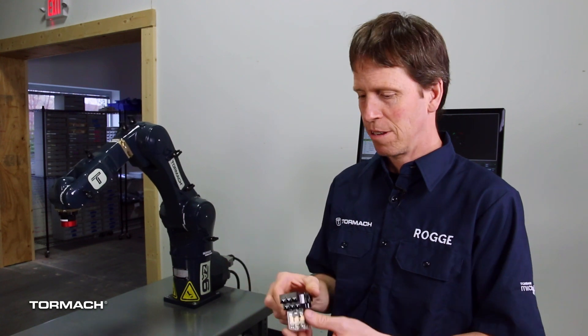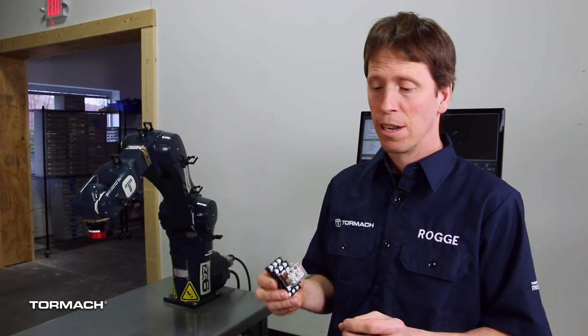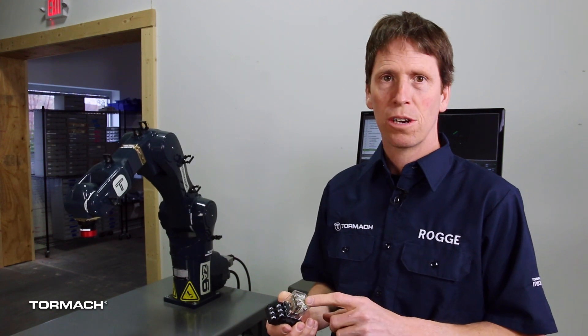Firstly I've got a 24-volt contactor, it's a din rail mount, it's just a simple contactor, but what's important it's a 24-volt DC contactor. Any relay or contactor you're going to want to use for this will be something that has a 24-volt coil. You can't use a 5-volt coil or 12-volt coil or an alternating current coil, it's got to be a relay or a contactor that takes 24-volt DC for its coil.